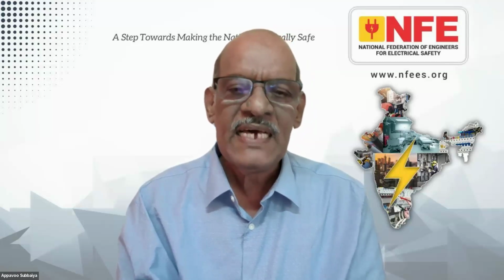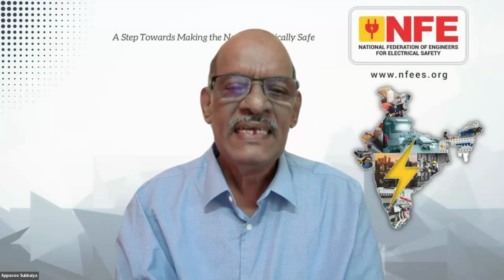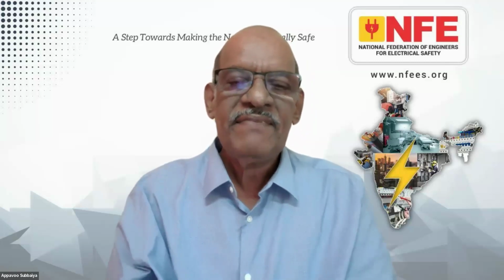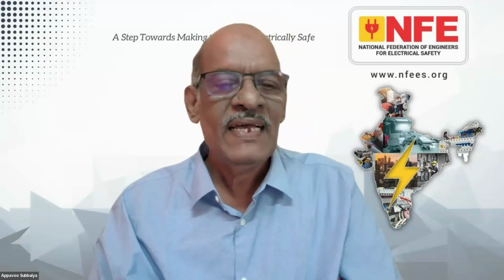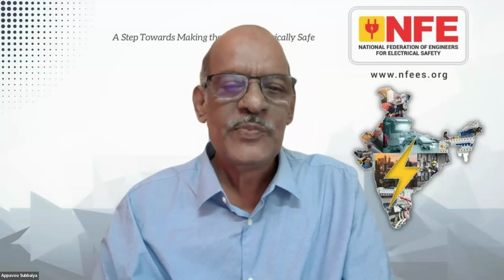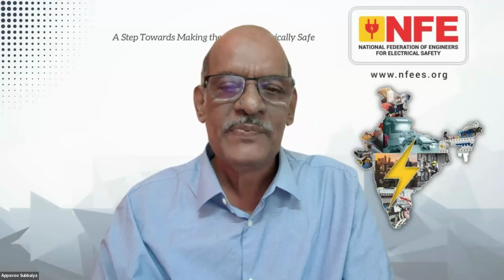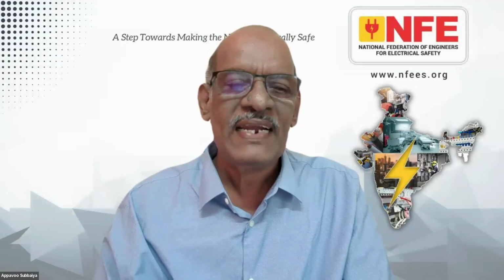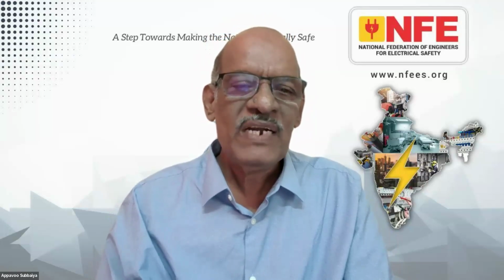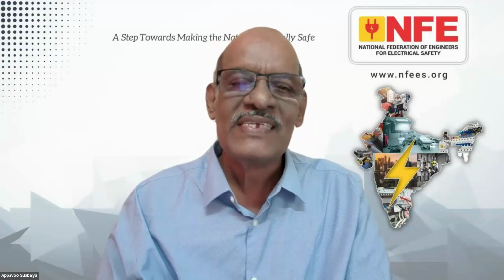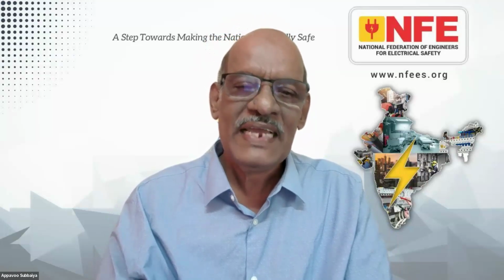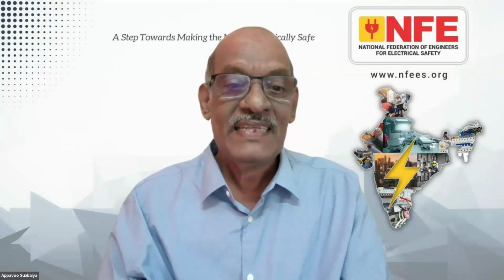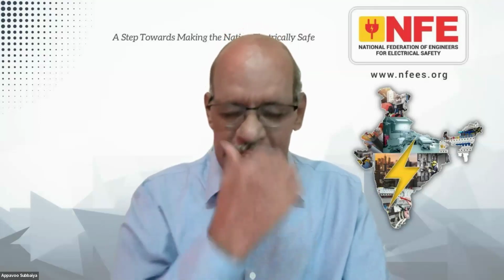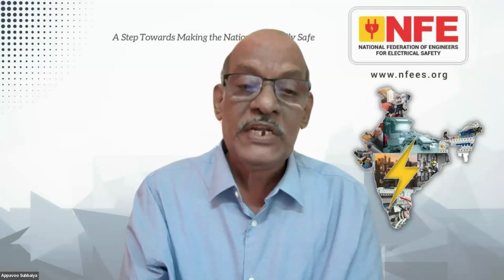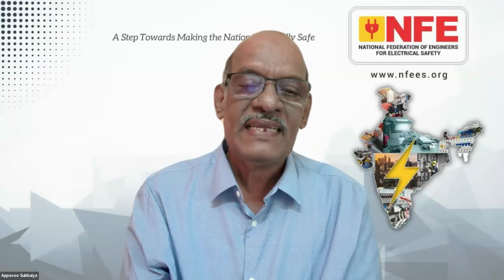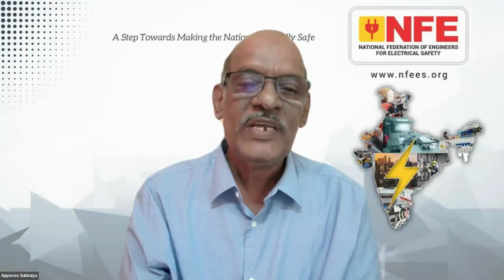Because any design aspect, installation aspect, everything is finally getting vetted by the testing, whether it be a verification for an LV installation or touch potential rise for an HV substation. It's all ending with a final validation through testing only. But the test instrument doesn't possess any NABL accreditation for either calibration or testing. That is the pathetic situation. Unless the specific aspect is looked into, all the basic design, installation, inspection will become futile.